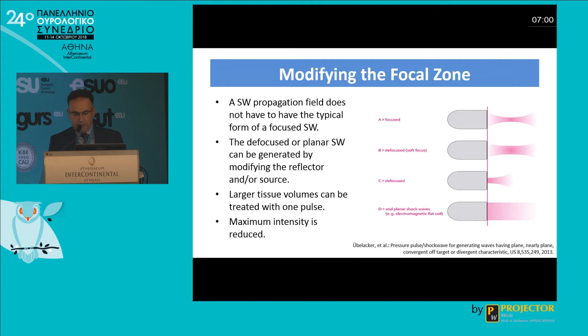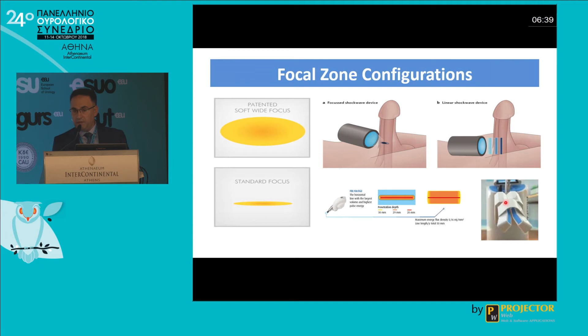We can see some examples over here, how we can transform the cigar-shaped focal zone of an electrohydraulic device to a wide, soft focal area, and how we can convert the tiny little focus of a piezoelectric machine to a linear one. And there are even now devices that can combine two probes in order to cover both corpora simultaneously.